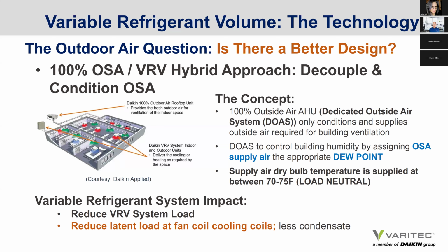What about a 100% outside air variable refrigerant hybrid approach to decouple the outside air from the VRV system? So in this concept, we actually handle all of the outside air with a 100% outside air unit. We use energy recovery for the most part to precondition the outside air before it even hits the 100% outside air unit cooling coil, and then we distribute that outside air locally and directly to each zone. So this way, if you properly control your outside air humidity levels, you can offer better humidity control with a variable refrigerant system, because your supply air can be designed to a dew point that will absorb the humidity gain in a building during our wettest times of year, July, August through mid-September.